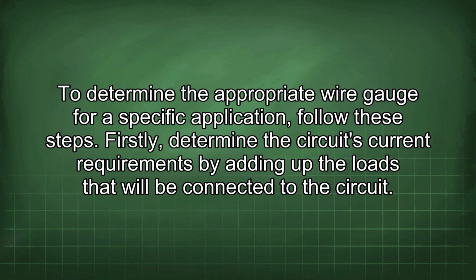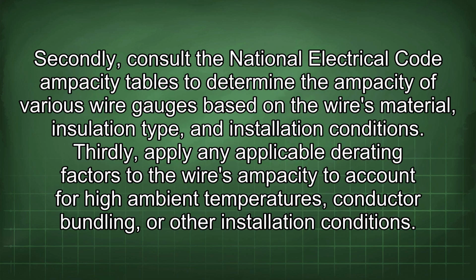To determine the appropriate wire gauge for a specific application, follow these steps. Firstly, determine the circuit's current requirements by adding up the loads that will be connected to the circuit. Secondly, consult the National Electrical Code ampacity tables to determine the ampacity of various wire gauges based on the wire's material, insulation type, and installation conditions. Thirdly, apply any applicable derating factors to the wire's ampacity to account for high ambient temperatures, conductor bundling, or other installation conditions.